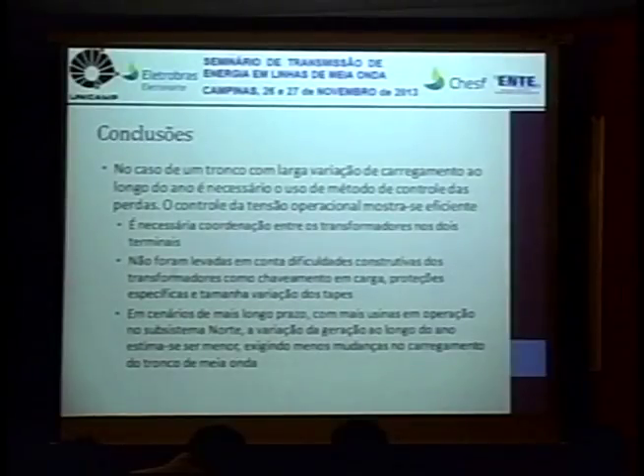In a case with a line with large variation of loads throughout the year, which is the case of Belo Monte, it is necessary to use control methods for losses. This is going to be done by controlling the operational aspects of the line, controlling what's out of phase. Operational voltage control shows to be very efficient. It's necessary to coordinate the transformers between two terminals. This cannot be uncoordinated.